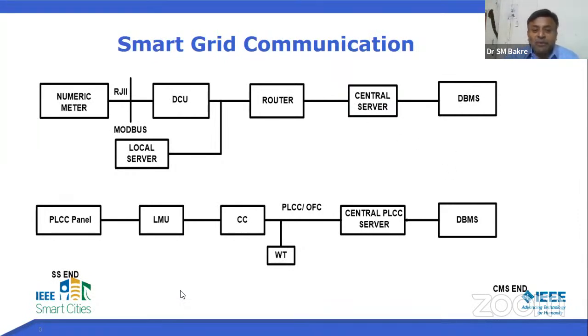The substation numeric meters are there for sending data - basically the ABT meter sends ABT data, but data can also be sent through TOD meters, smart meters, or any other microprocessor-based meter. At present the communication is taking place from ABT meter to CMS, and in all there are 9,000 nodes where communication is going on all over Maharashtra - such a huge network for smart grid communication. RJ11 is the connector provided at the back of the numeric meter, connected to the serial port, and it's connected to Modbus. From Modbus it's connected to the DCU through Ethernet or another communication channel. DCU is the Data Concentrator Unit where all the data is sent.